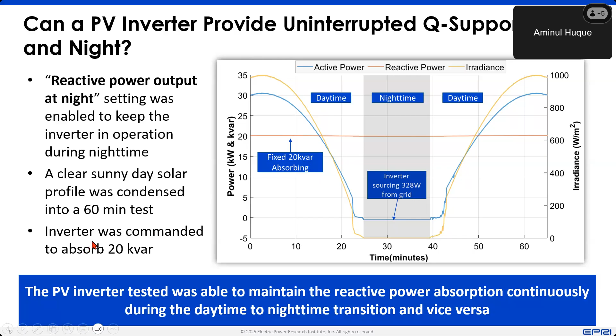So this is what I meant by cost. It's not free. So this active power has to come from somewhere. Somebody has to pay for that. So those are the business side discussion. So then we wanted to say, okay, not just one target reactive power. What if I vary the reactive power demand? What if it's not just absorbing, but also injecting? So basically we operate this inverter in fixed reactive power mode, but we define a target reactive power value. And for each of the tests, we captured how much real power or active power it takes from the grid. So that's the plot you are seeing on the screen right now.